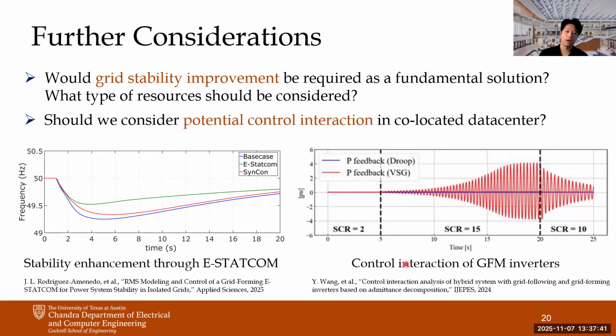As a result for this kind of grid stability improvement, we believe that E-STATCOM could be the best solution for these kinds of issues, since, as I have mentioned earlier, there are some voltage and frequency coupled issues arising, and basically E-STATCOM can handle both the voltage and the inertia or frequency stability issues. This could be a good mitigation solution for these kinds of problems caused by the data centers.